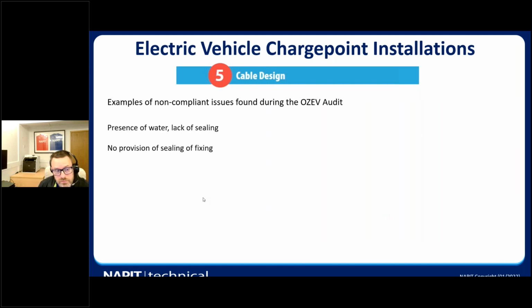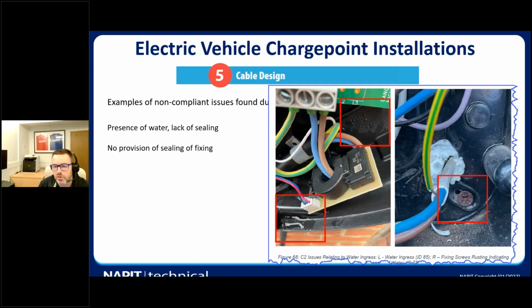So, presence of water, lack of proper sealing, fixing. So you've got some here. You can see in the highlighted areas there's moisture in here, there's water ingress here, and this cable here is not correctly sealed. You've got the screws rusted, it's not been properly sealed or properly included for correct sealing when you try and fix against the surface. You've got rusting in here. So there are always these issues that were picked up in the audit.